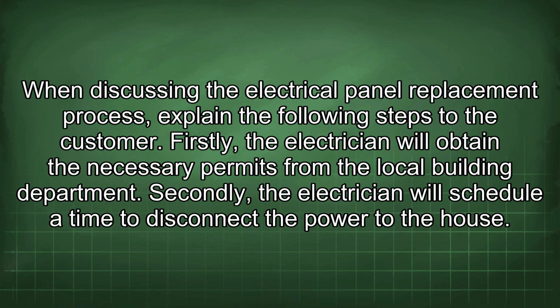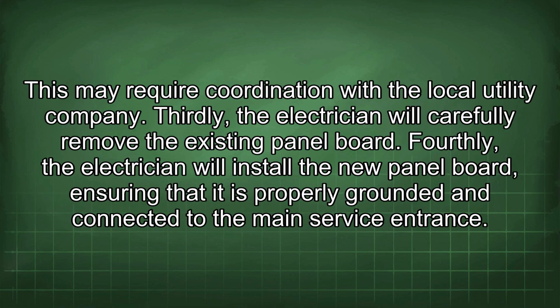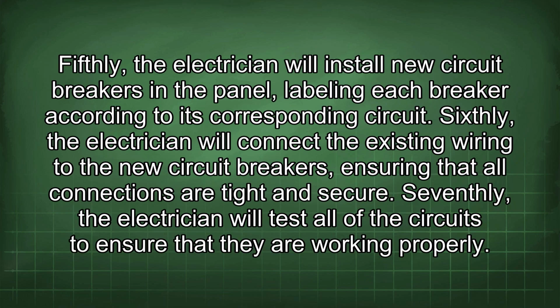When discussing the electrical panel replacement process, explain the following steps to the customer. Firstly, the electrician will obtain the necessary permits from the local building department. Secondly, the electrician will schedule a time to disconnect the power to the house. This may require coordination with the local utility company. Thirdly, the electrician will carefully remove the existing panel board. Fourthly, the electrician will install the new panel board, ensuring that it is properly grounded and connected to the main service entrance. Fifthly, the electrician will install new circuit breakers in the panel, labeling each breaker according to its corresponding circuit.